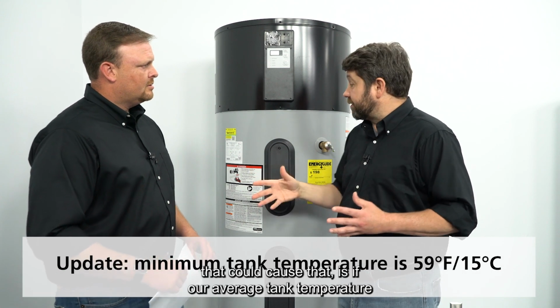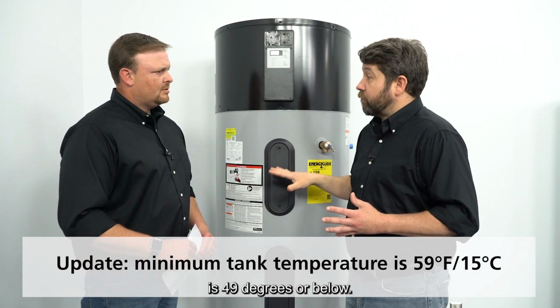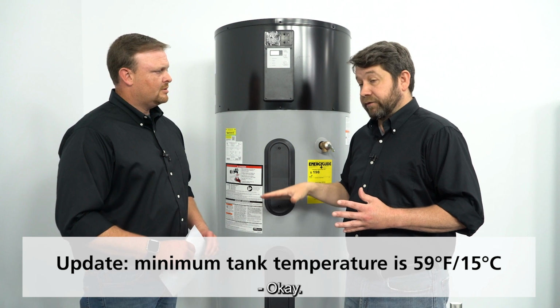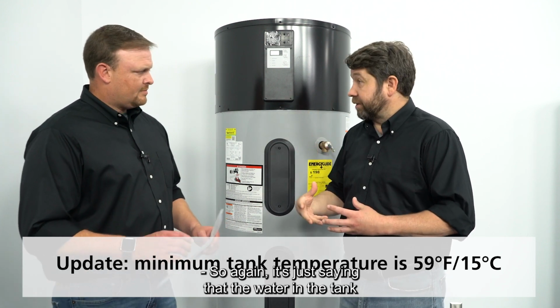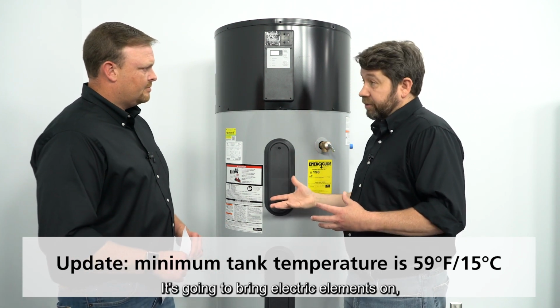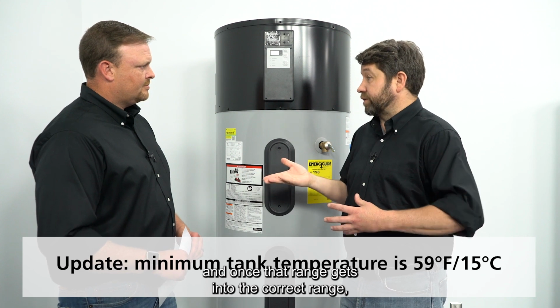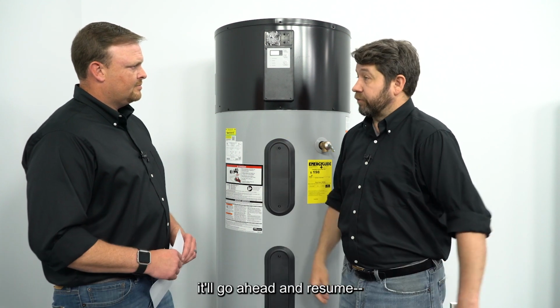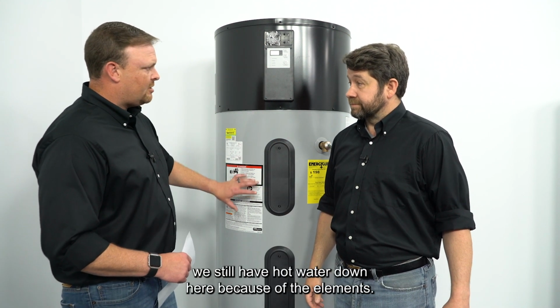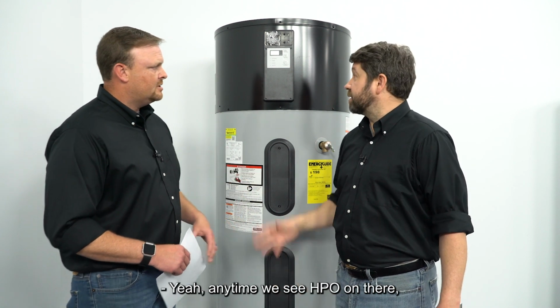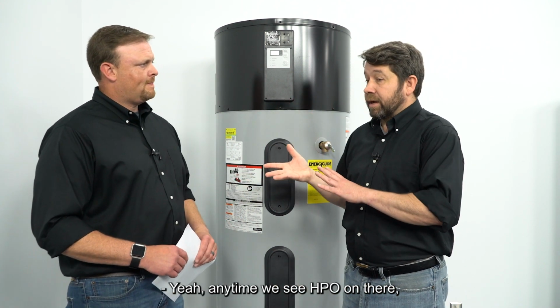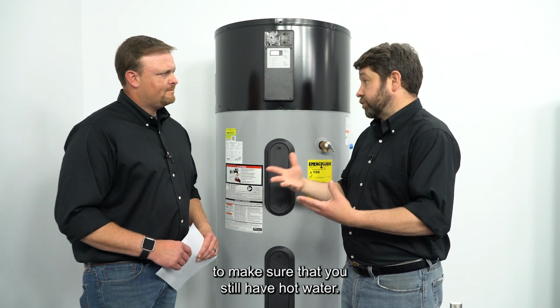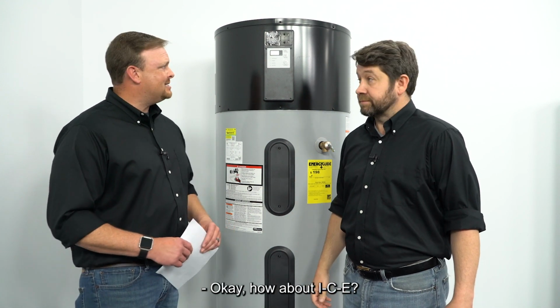Something else that could cause that is if our average tank temperature is 49 degrees or below. So again, it's just saying that the water in the tank may be really cold. It's going to bring the electric elements on. Once that range gets into the correct range, it'll go ahead and resume heat pump. Even though you see that, we still have hot water because of the elements. Anytime we see HPO on there, it's going to automatically switch to the elements to make sure that you still have hot water.